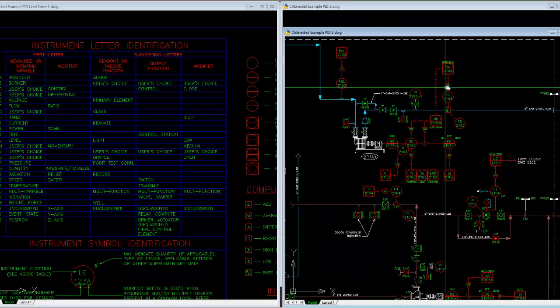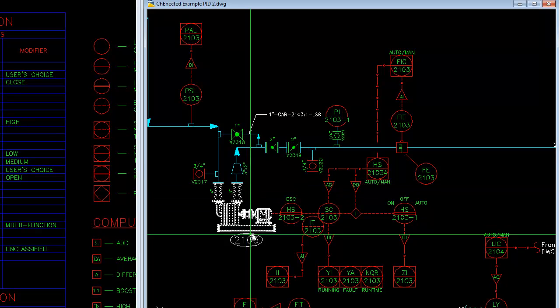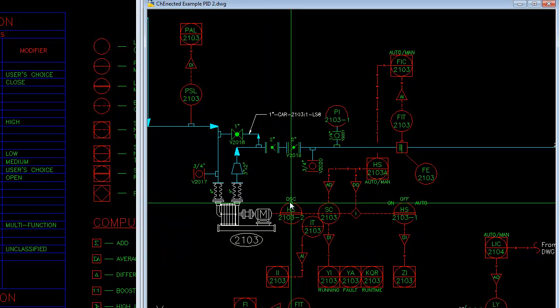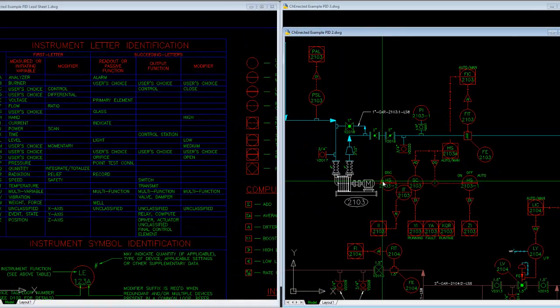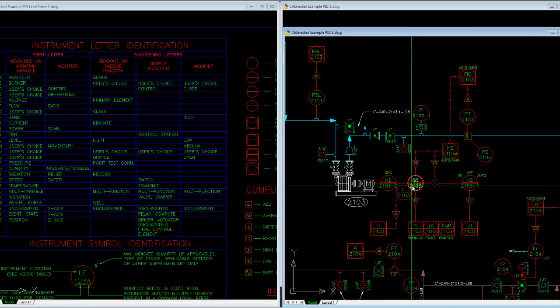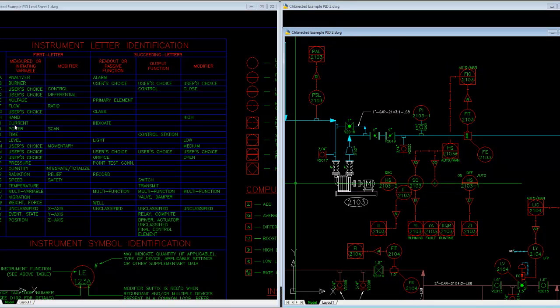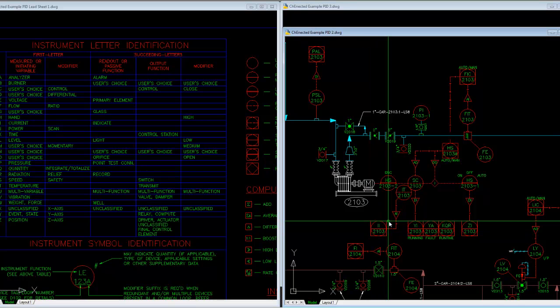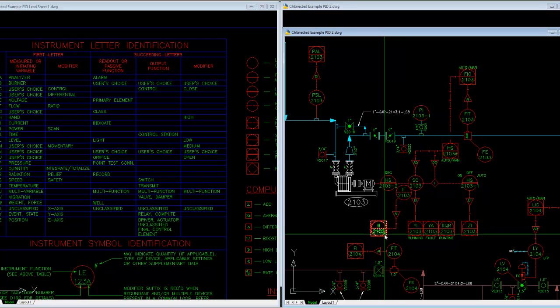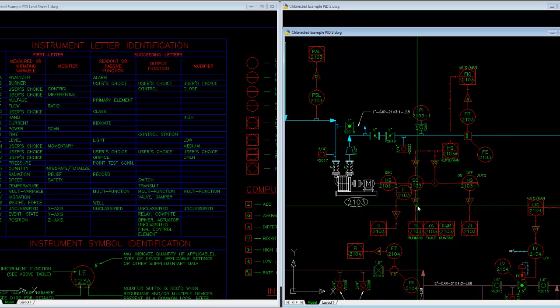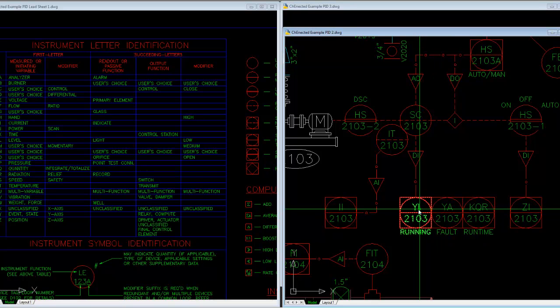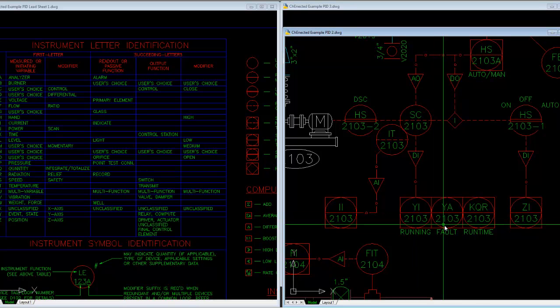The point is to not get too caught up in detail but to understand the high level, using functional descriptions on how the plant is intended to run. Now, zooming in on 2103 — this is a blower. The blower has a local disconnect (an abbreviation I define on my legend sheets). The speed controller associated with that motor has a current transmitter (first letter: current) providing an analog input so you can see how much power the blower is drawing through the current indication on the control system. When that motor is running it provides a digital input to the PLC, and you can see various things available on the HMI.